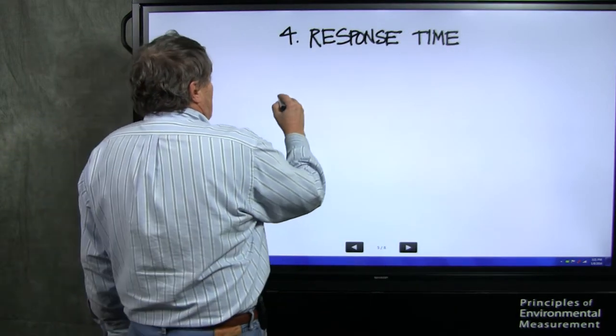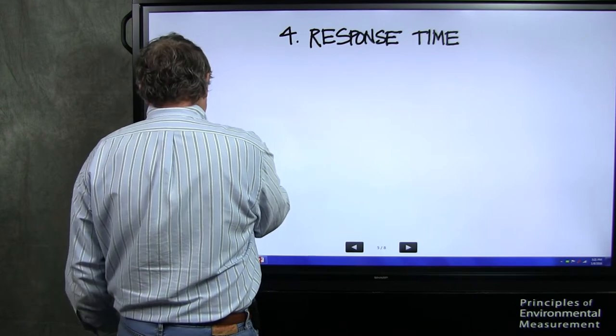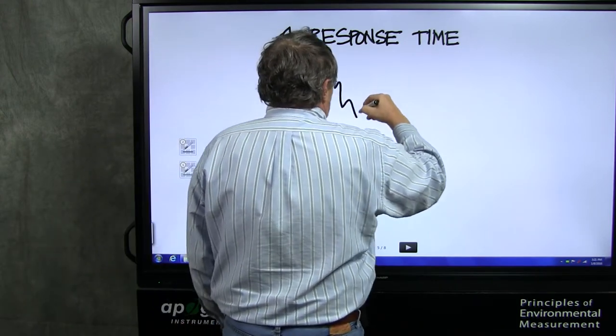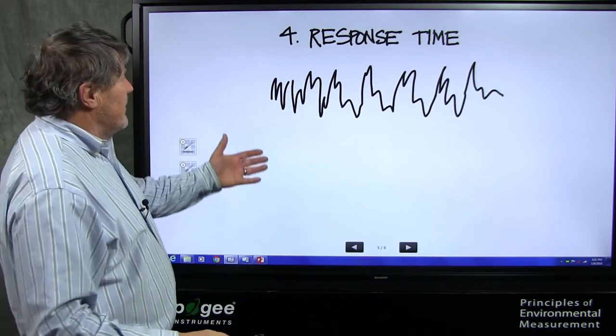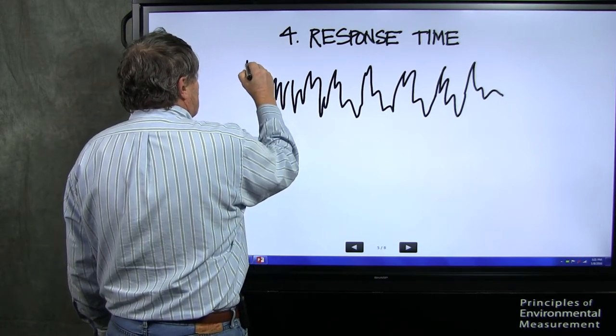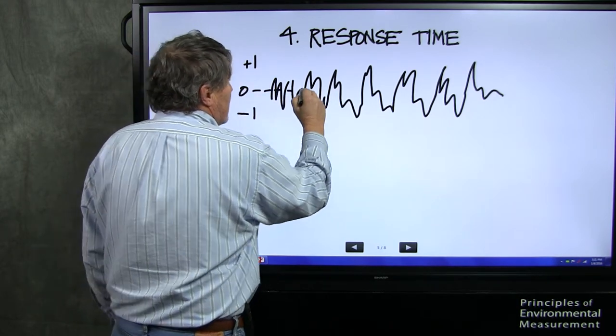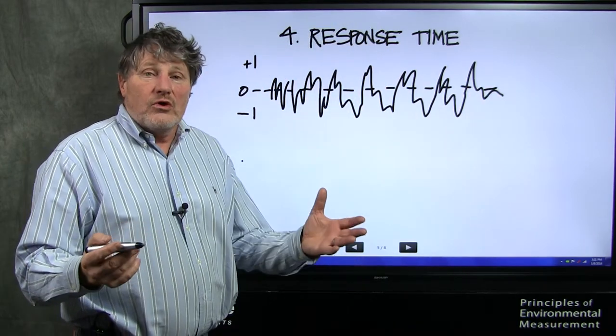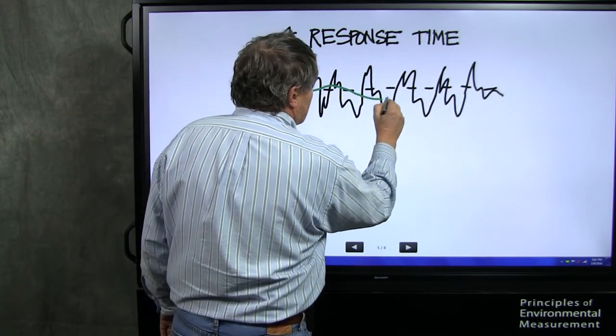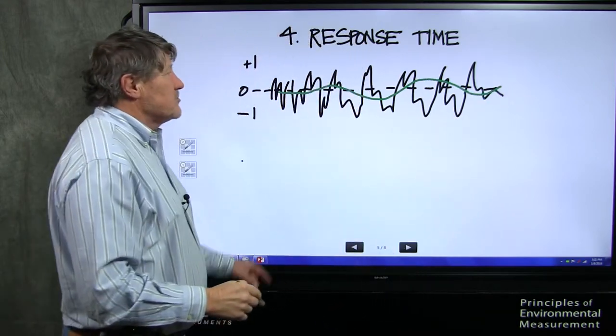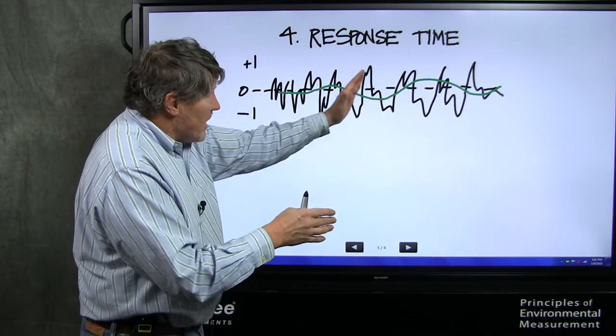Number four, response time. If this is time here, signals can look like this. A cheaper signal has a lot of noise. And this might be plus one degree and minus one degree, and zero is right here. So if this signal is bouncing around, what do you do? You do a running average, and I'll show that in here in green. You might have a running average that looks like that. That's much more accurate, but you have to wait to get your data. You have to leave it on there for several seconds to average this.